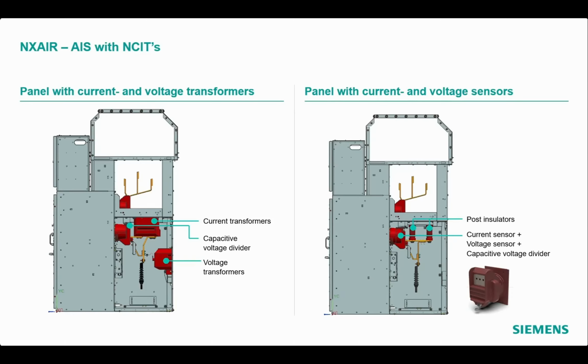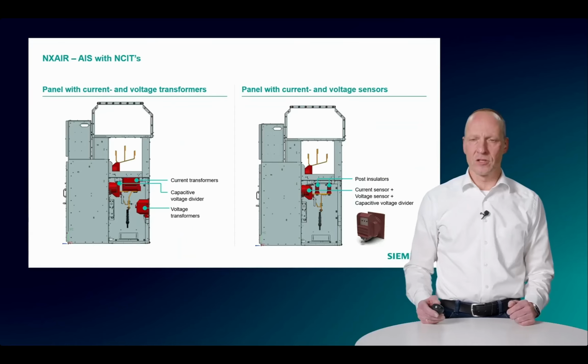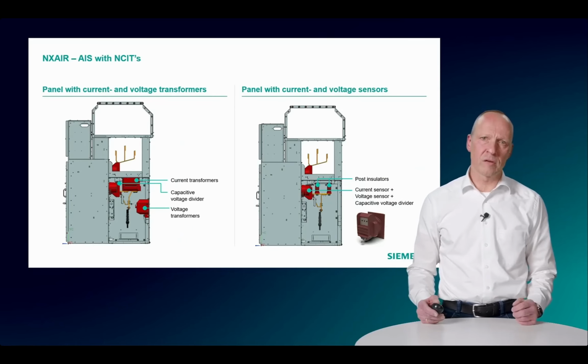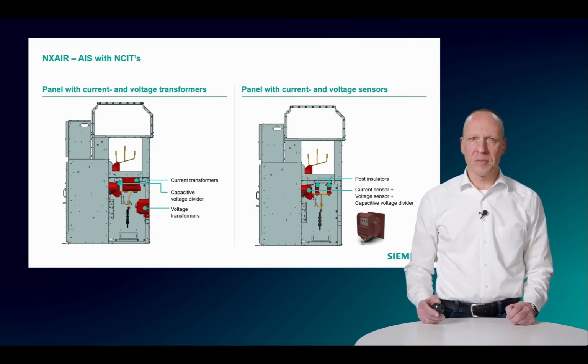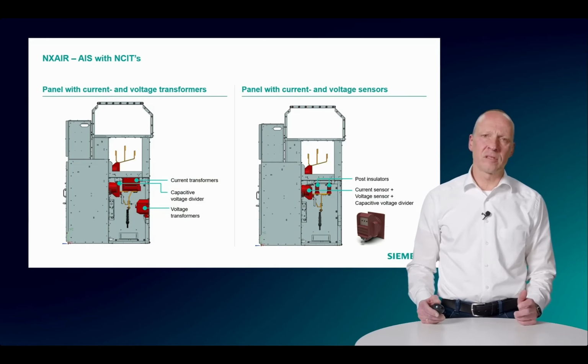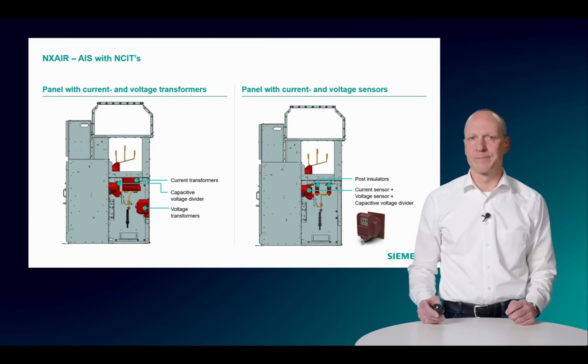Last but not least, we have also a LPIT solution available in our NX Air. Conventional CTs and VTs in AIS are designed typically as cast resin block types. To remain in the same switchgear design and to give the option to our customer to decide whether conventional or low power instrument transformers should be used, we replace the conventional CT with two small post insulators, remove the voltage transformers, and integrate a resistive divider and a Rogowski coil in the bushing.